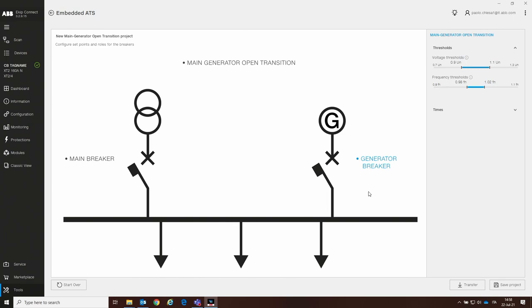Regarding the functionalities and accessories needed, Ekip Connect with the embedded ATS tool can automatically recognize the required accessories if they are connected, and also whether functionalities such as the measuring functionality are installed on the trip unit. What we find here is a generic page about the main-generator open transition. The customer needs to click on the main-generator open transition button and then can start to set some settings. The most important settings are the three thresholds in terms of frequency and voltage, which will trigger our automatic transfer switch.